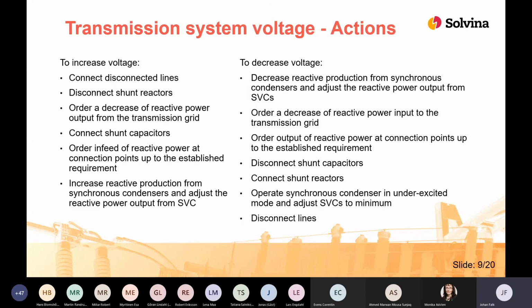So if we are looking at which actions Svenska kraftnät can take to manipulate or change the voltage, we have this list that we have received from Svenska kraftnät. If I'm not wrong, it's from an appendix to a document called Driftinstruktioner, like operational instructions. And we can see that Svenska kraftnät can disconnect shunts, and these connections or disconnections are always done manually. So it's the operators who give the command to disconnect or connect shunts. Svenska kraftnät can order an increase or decrease of reactive power to the transmission system. They can also adjust synchronous condensers and SVCs to change the voltage.